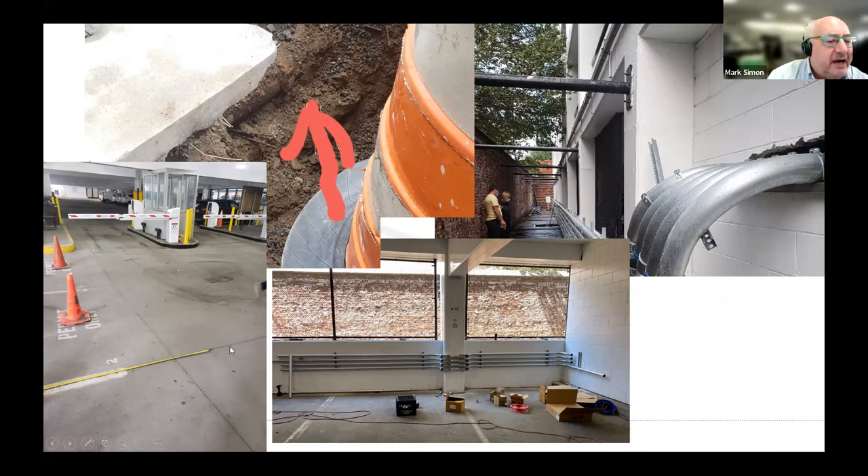Right where the arrow is, you're going to see a mistake that we made. When we originally designed it, we wanted to use the spaces closest to the entrance to the garage. However, once we did the final layout and design with the actual equipment in place — by the time you put the cement pads and the bollards — it was going to cause vehicles to extend into the access to the garage. We felt that was unsafe, and we ultimately switched the first two spaces to level twos with wall-mounted chargers and put the fast chargers further away. Just be careful when designing for the extra space that cement pads and bollards take.